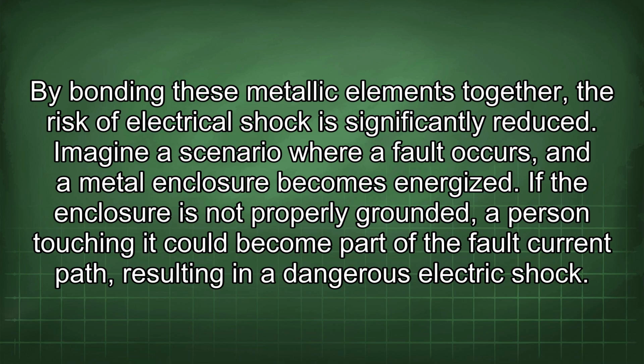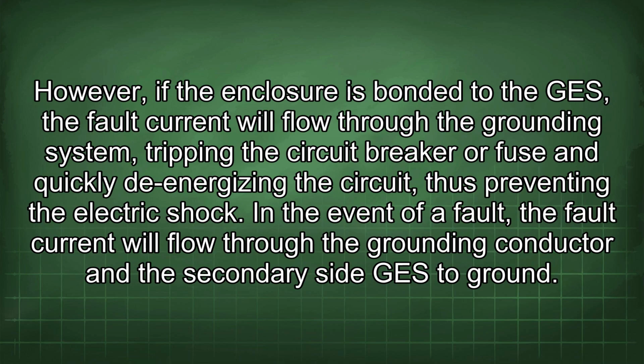Imagine a scenario where a fault occurs and a metal enclosure becomes energized. If the enclosure is not properly grounded, a person touching it could become part of the fault current path, resulting in a dangerous electric shock. However, if the enclosure is bonded to the GES, the fault current will flow through the grounding system, tripping the circuit breaker or fuse and quickly de-energizing the circuit, thus preventing the electric shock.